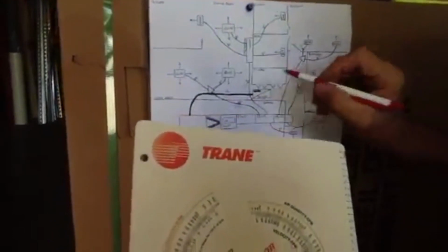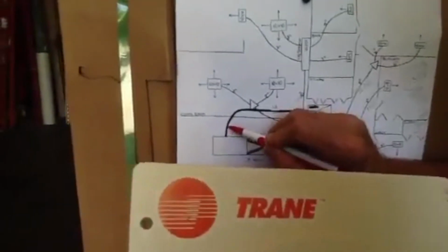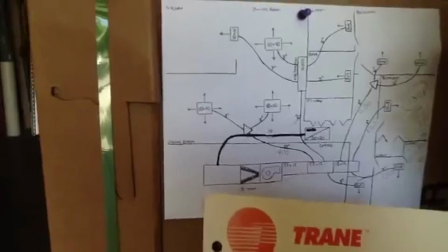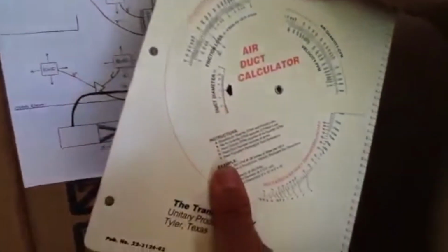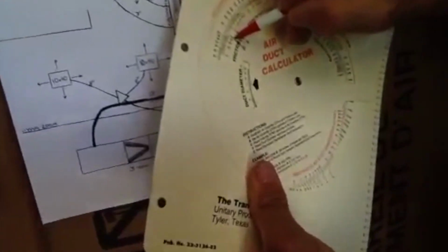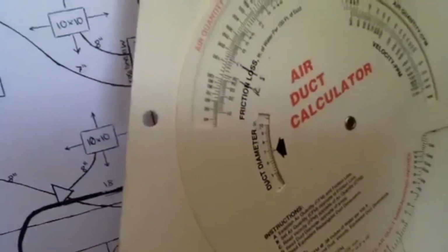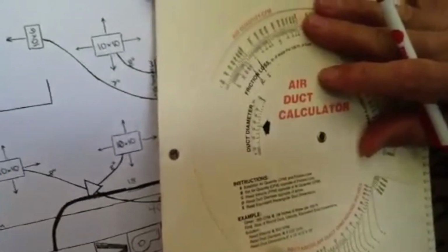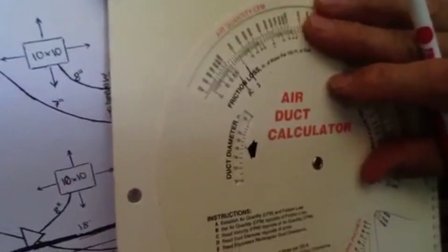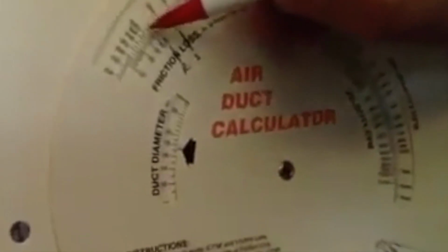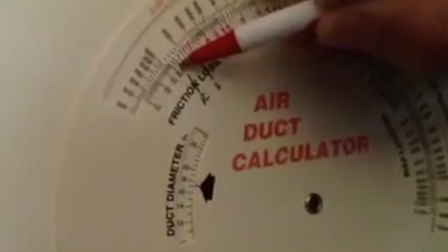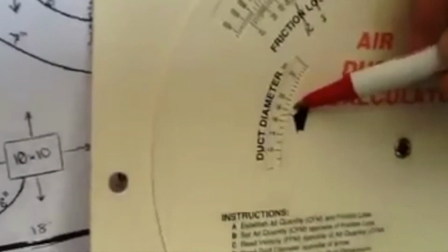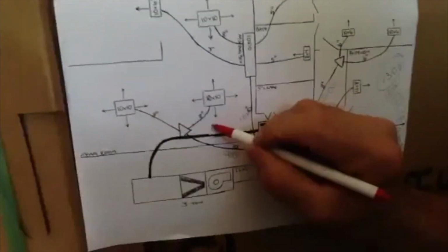Okay, now let's talk about return. You want to always do your return, size it based on 400 CFMs, but in this case we want to use a 0.05 static pressure. So now let's go. A 3-ton system is how many CFMs? 1,200. Okay, 1,000, 1,100, 1,200. See that 1,200? What size flex do I need? 16 or 18? You always go up on the return. 18-inch. Okay, so that's what we've got right here.